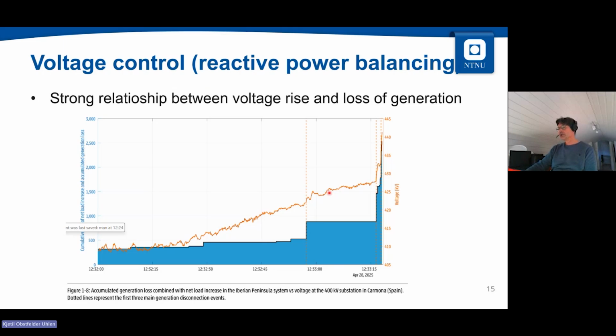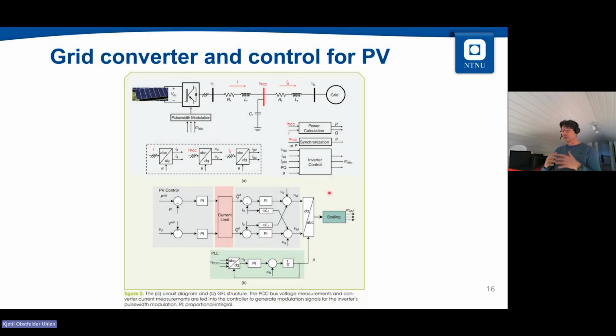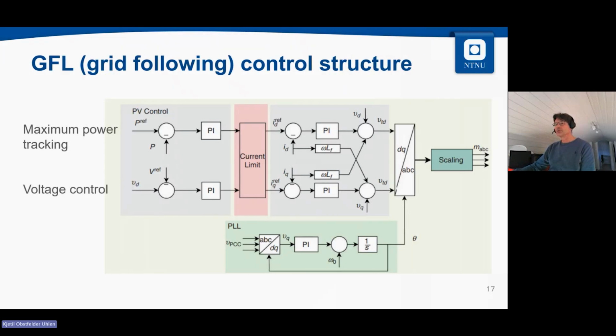The solution, I think, is very much also on the inverter-based resources themselves. If we look at PV plants, which were a major part of the generation in Spain that day, the controls there are quite basic. It's quite easy to also add a voltage control loop that can provide reactive reserves in both directions, in addition to the maximum power tracking of the PV plant itself.